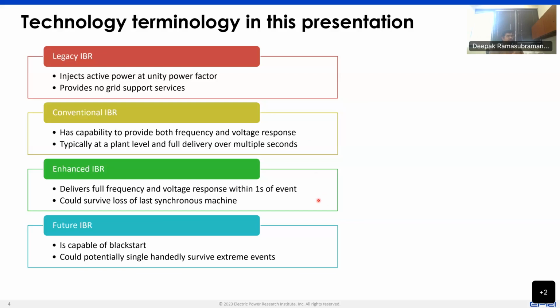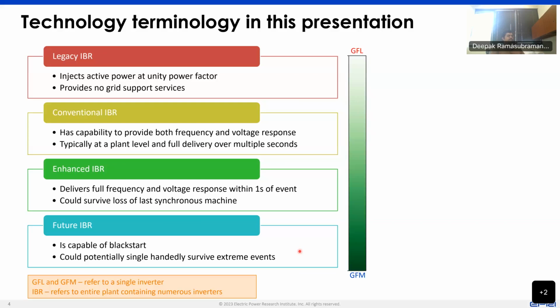Then we can go towards a different classification of inverter-based resources called enhanced IBR, which can deliver this full frequency and voltage support and response within 1 second of the event occurring. And I will show some examples of that. And if it's part of a network with other enhanced IBRs, then the network itself could survive the loss of the last synchronous machine. And finally, we go to a future IBR that is capable of black start and can potentially single-handedly survive extreme events. It can be designed to tolerate very large extreme events, be stressed a lot, and single-handedly survive a lot of such events. So if we take this classification of 4 different categories of inverters, and now we try to apply the terminology of grid following and grid forming that we might have heard across the industry, it actually lines up like this.